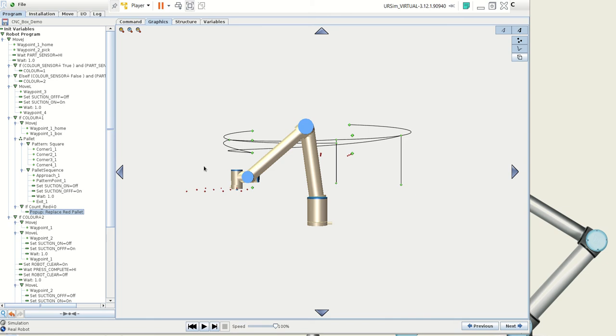We've got a bit of free space in here. I'm going to assume we've got additional machinery over here, so this is going to be cordoned off, and there's going to be no new users in there, because that's why we have the robot and the CNC machine working together. But there's this free space over here, so I'm going to put in a safety scanner that scans this area to the left, and if someone comes in and gets too close, it's going to bring the robot into reduced mode. You can have a play around with some safety boundaries or other scanners if you want, emergency stop buttons, that's no problem.